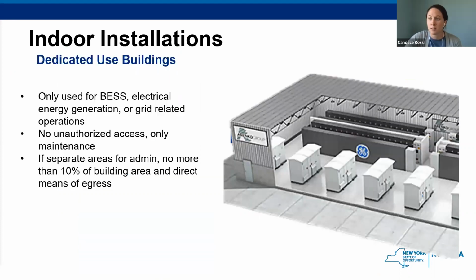So first we'll discuss the dedicated use buildings. So these are buildings that are only used for battery energy storage, electrical energy generation, or grid related operations. There's no unauthorized access, only maintenance. And if separate areas are needed for admin, no more than 10% of the building may be that, and there must be a direct means of egress. So once again, this is not where you're planning your lunch date. You're not gonna be just hanging out in one of these buildings. They're really meant to be dedicated for energy storage, and that is all.